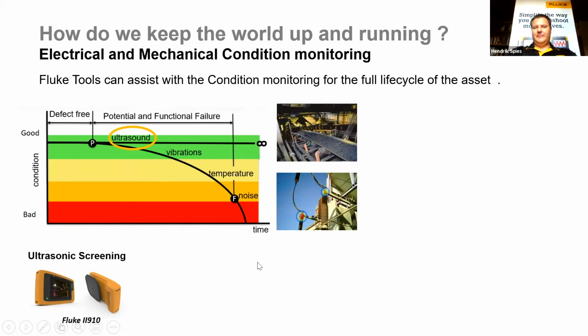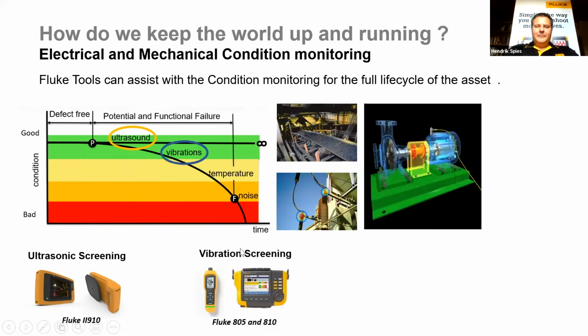So first, ultrasound. What is the second level? Vibration. So with Fluke, we've got the Fluke 805 and 810 for vibration screening and analysis. And typically, if you look at an installation like this, we've got a pump with a motor and you've got a coupling in between. There's certain points here that you want to measure, and typically you want to measure vibration over the bearings. So that will give us an overall picture of vibration and if it's good or bad, and where does this bad vibration come from.